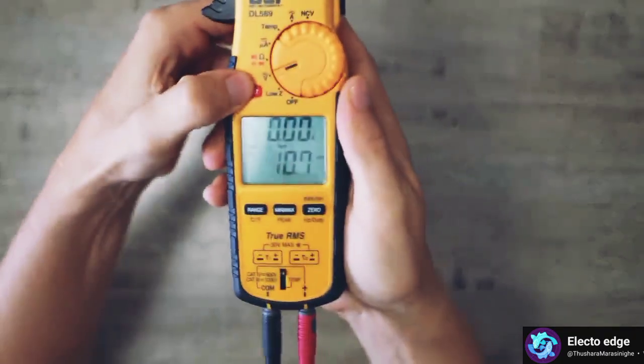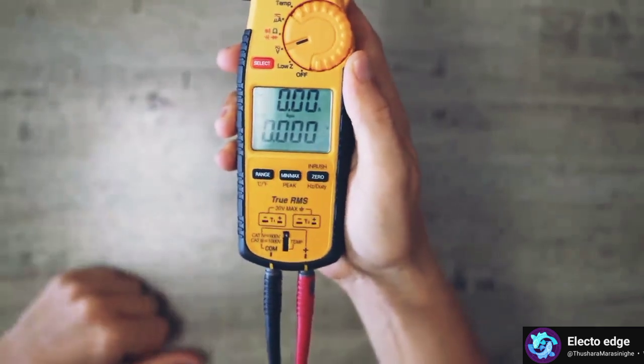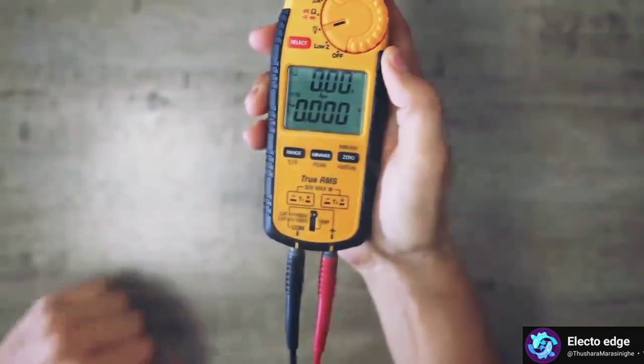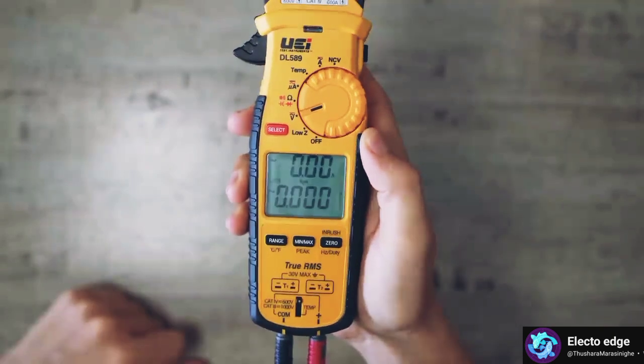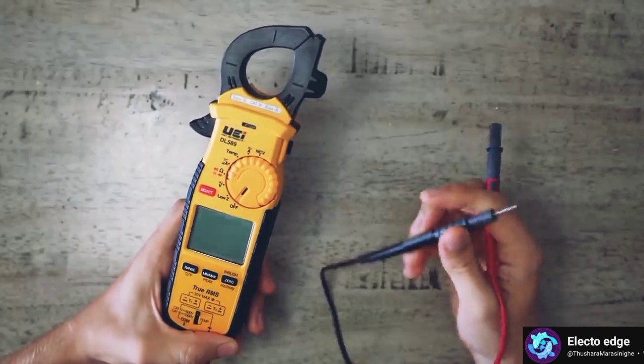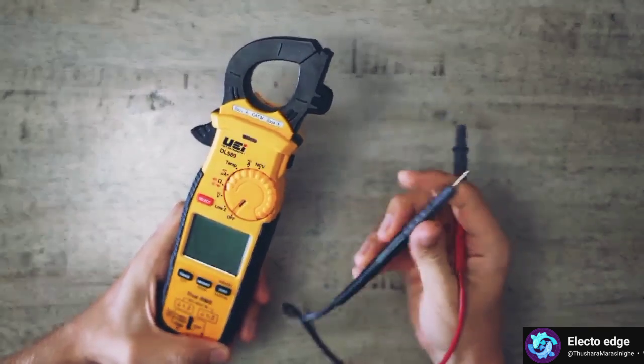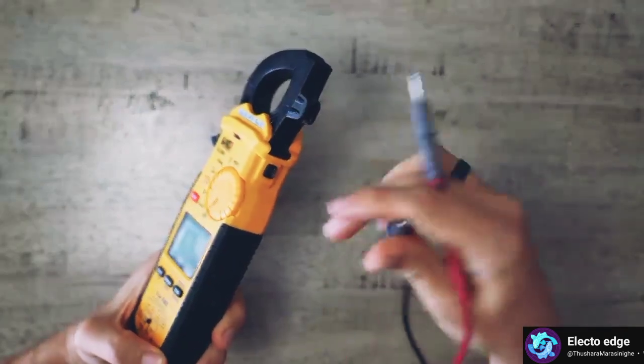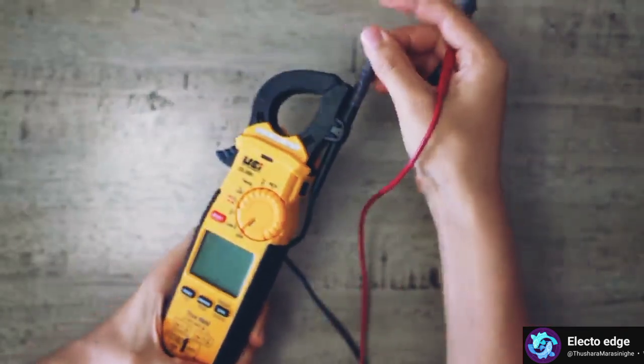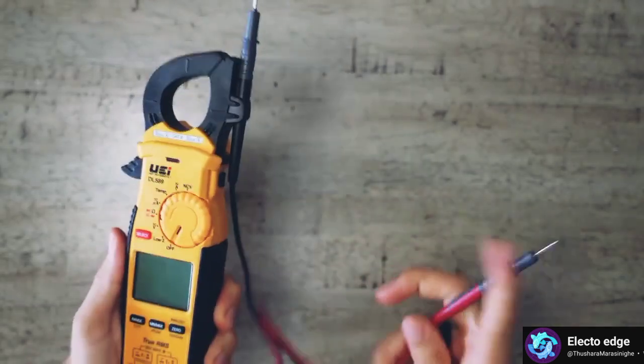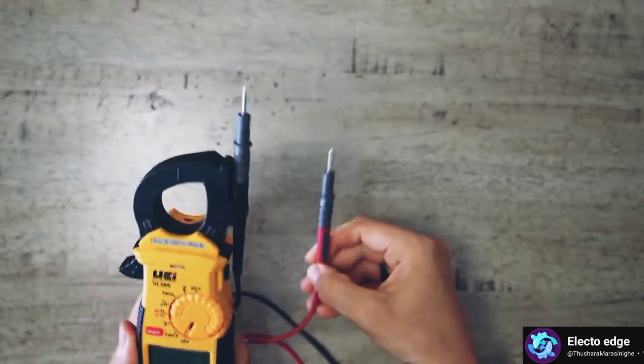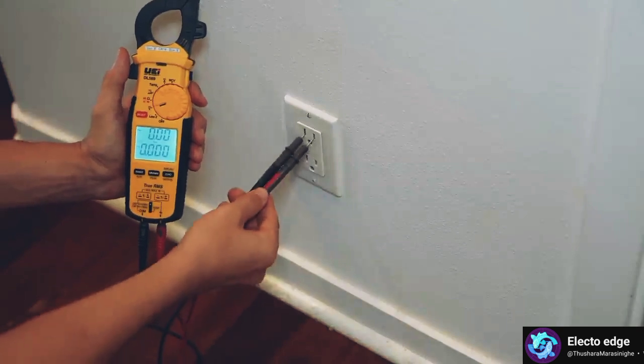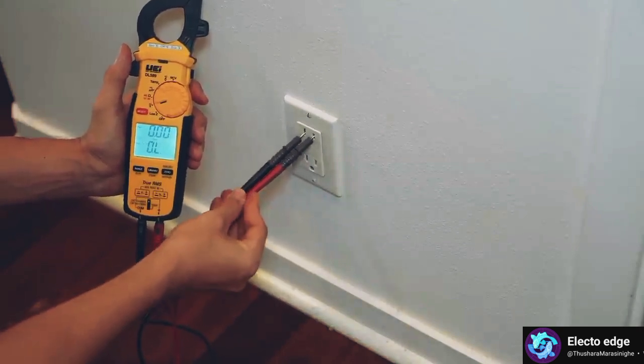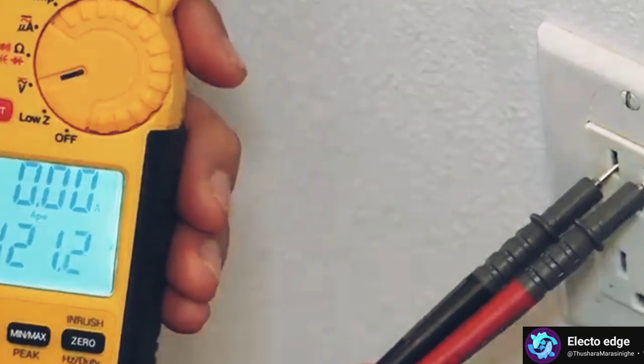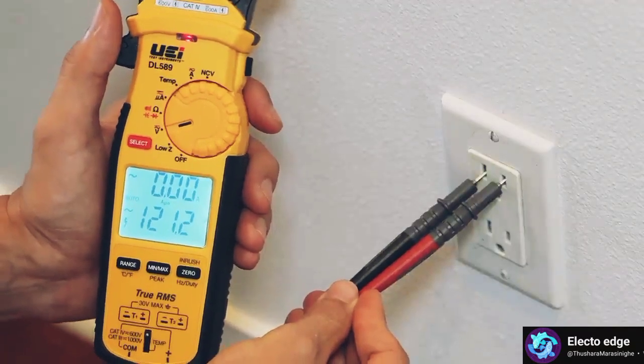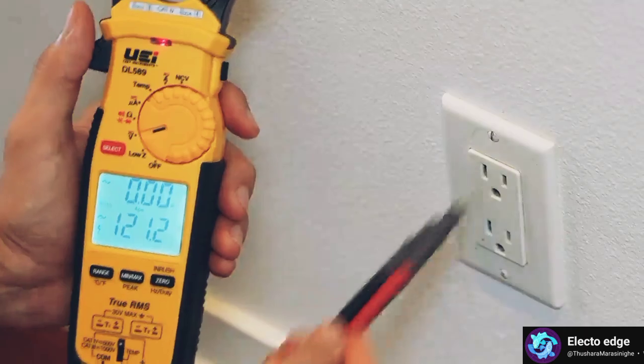And when testing alternating current, do exercise caution because live electricity could be dangerous. Don't touch any exposed metal or exposed wires. When testing alternating current, it's a lot safer to use one hand only. And what helps with that is if your meter has a little holder like this, you can plug one lead in to the holder and use your meter as one hand and use your lead as the other. Testing AC voltage is a perfect way to see if something is getting power or not. It can be used to test furnaces, air conditioners, household appliances, circuit breakers, thermostats, and etc.